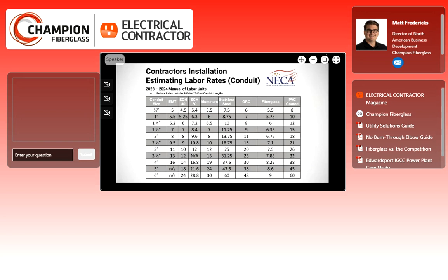This chart is a chart that Champion Fiberglass created, using data from the NECA Manual of Labor Units, all aggregated together. If you're looking at this chart, it's a great way to estimate how long it's going to take to install 100 feet of conduit, derived from man hours. What's important to note is that the man hours indicated on this chart are all for installation at chest height—it isn't for underground. What we find is that installing underground, the labor rates are actually much lower than this.